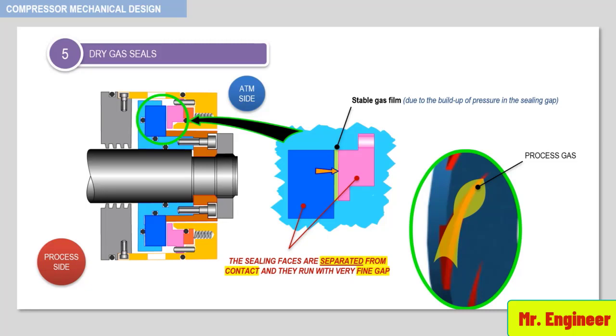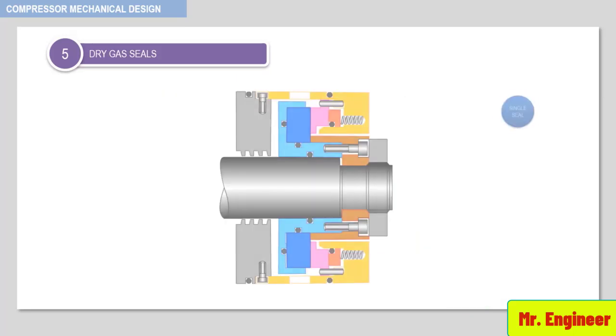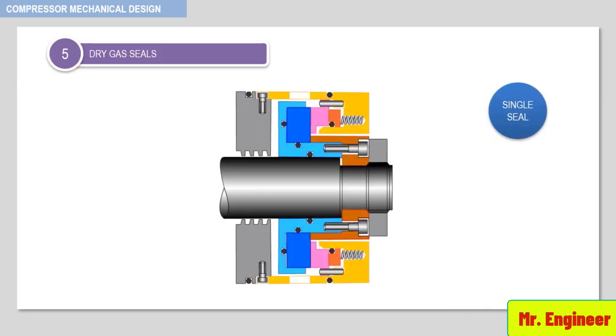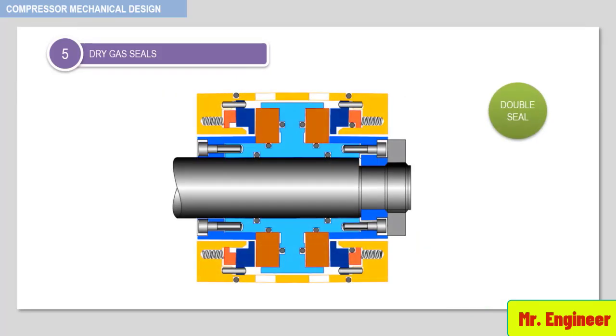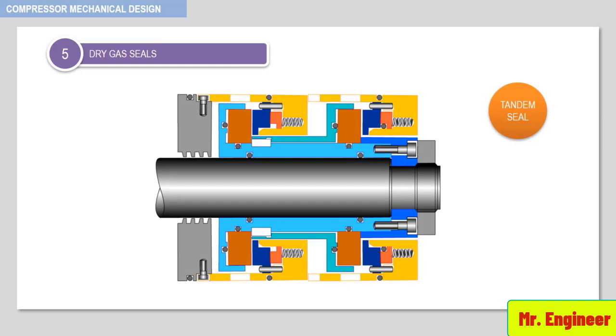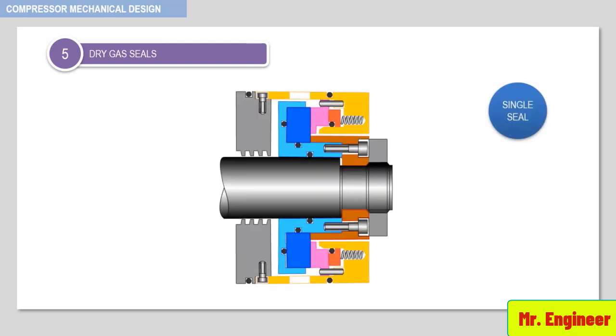Dry gas seals exist in various arrangements: single seal, double seal, or tandem seal. The single seal is used for compressors which have lower sealing pressures and where a small leakage of gas medium can be tolerated.